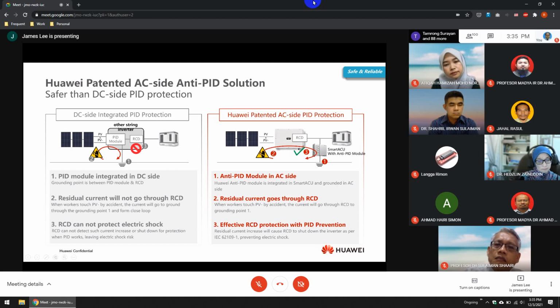Now what happens when that kind of design is implemented? First and foremost, it's high risk of electrocution to personnel operating the inverter or at site, because the RCD is on the AC side, and if there were a leakage current, the RCD will never capture it, since it's not on the side where the PID module is doing the grounding to protect against PID impact. The grounding point is in between the PID module and the RCD, so it will never go into the RCD to give the protection required.